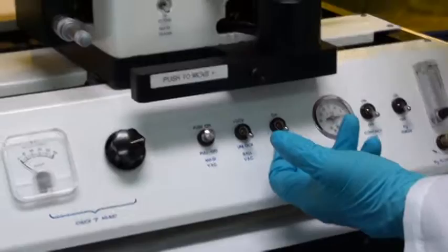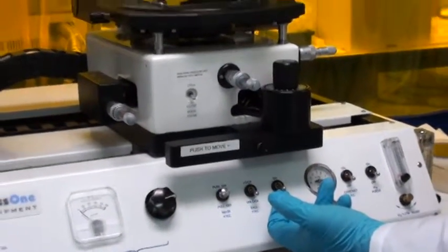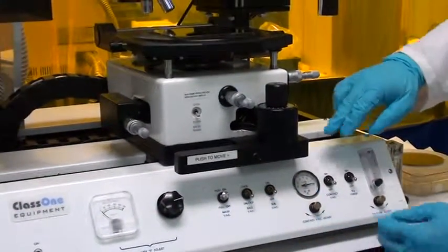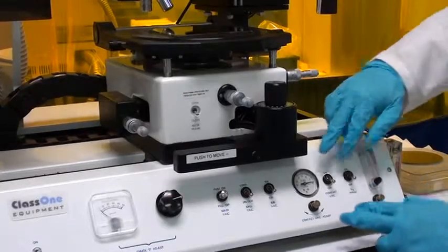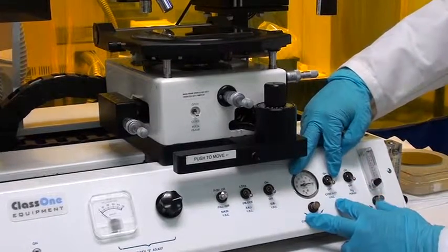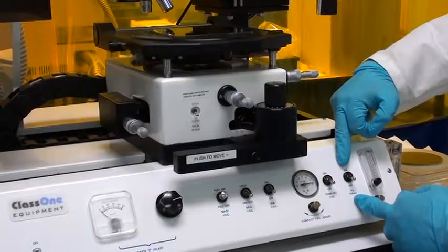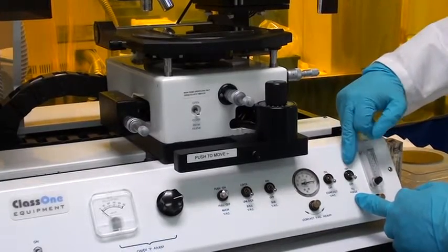Here is our substrate vacuum, which holds our wafer to the chuck. Next, if we're going to run contact vacuum, we have some adjustments for that to control the amount of vacuum. And we also have our nitrogen purge to release the vacuum when we're done with the system.